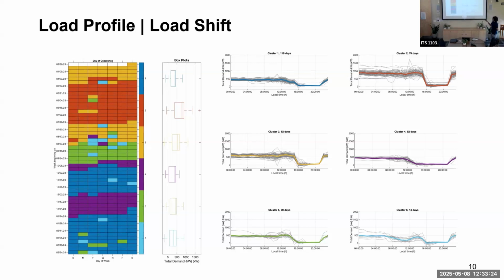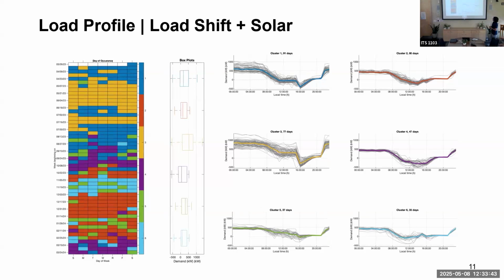And this is also an actual facility. This is a real load profile. So this is someone who's doing this in California, shutting down their cooling system during 4 to 9, and also not taking their load up during those off-peak periods. And if we add solar to the mix, that facility I was showing also has solar on site, and around 4 to 5 o'clock, their load starts going negative as well. So this is 0. At 4 p.m., 5 p.m., they're not only zeroing out their grid draw, they're also supplying electricity to the grid. So this is our target.